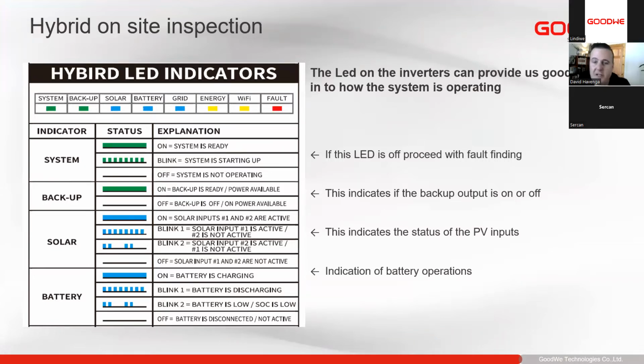So typically we don't look at the LEDs a lot, only if we are experiencing a problem. Normally we'll ask you what the LEDs indicate if we cannot get any data on the SEMS portal. So if we don't have data online, we can't see what's going on in the inverter, then we ask you to have a look at the LEDs so we can inspect to see what the condition is, especially when it comes to Wi-Fi. But normally, if you have a Wi-Fi problem, it's not online and we can't see why.